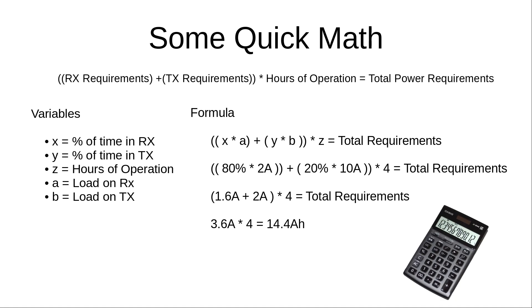It's also important that your battery can deliver your maximum load. In this case, you need a battery that can continuously deliver 10 amps to satisfy your Tx requirements. You can't just do the math formula and say you've got a 4 amp-hour battery and use it for 20 minutes — it doesn't really work that way. So make sure your battery is capable of delivering the required load.